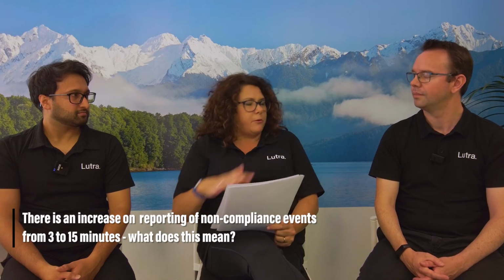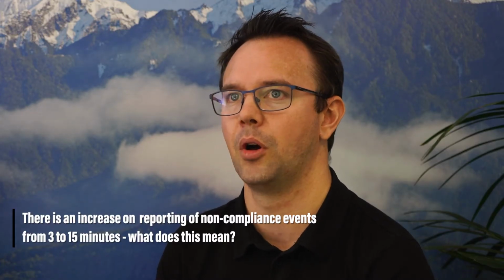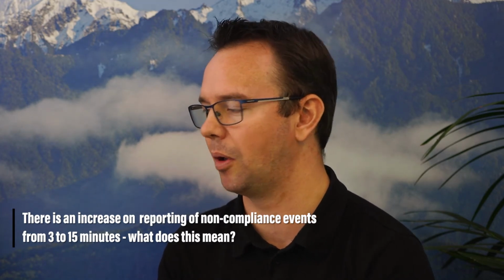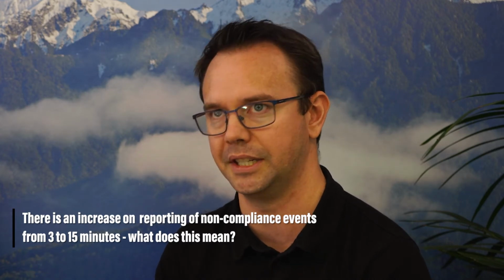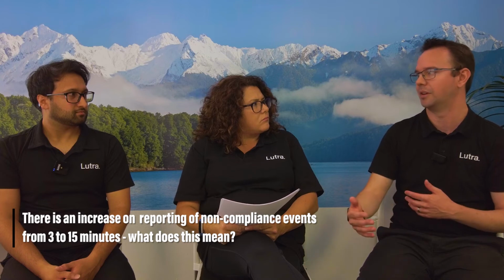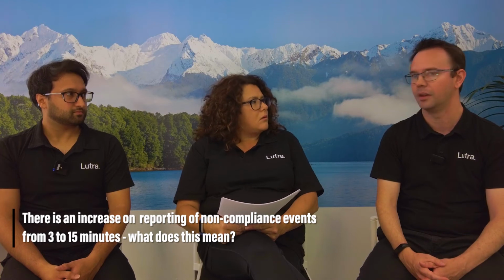Another question has come through around non-compliance events going from 3 to 15 minutes, depending on the processes. What does that actually mean? So at the moment there are various compliance processes that you need to demonstrate compliance with, and one of the demonstrations is that you don't have any 3-minute events. For instance, on a filter, this might be not exceeding a value of 0.5 NTU for 3 minutes. One of the changes in the new draft standards is that this has been changed from 3 to 15 minutes. And this brings us more into line with the international US EPA and various other requirements.